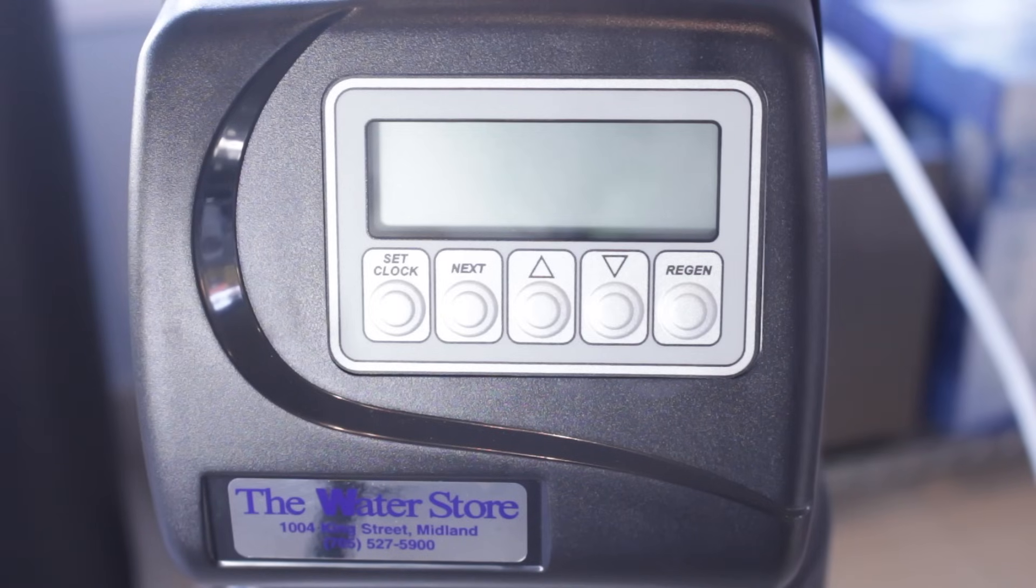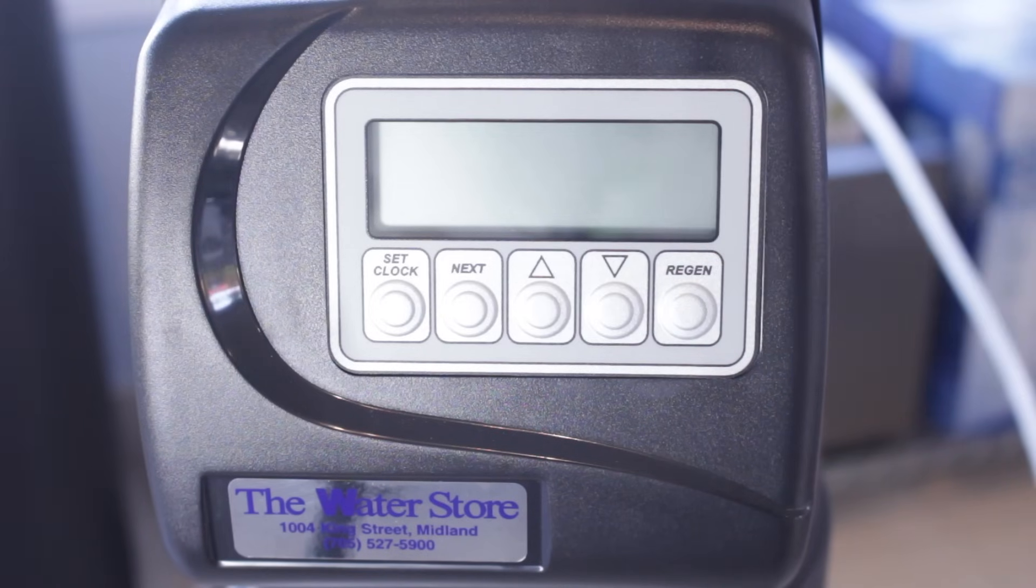Be sure to also check the faceplate. If it's a blank display on the LED display like this one is here, then there's a problem with the circuit board and the circuit board might need to be replaced.